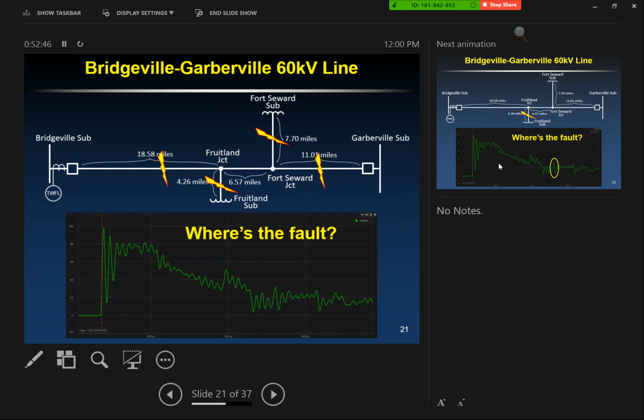See the noise here. We know this is the initial fault, right? This arrived back at the fault location relay at Bridgeville. But where's the fault in all this noise? Which is my point of interest? For this event, it happened to be this point right there.